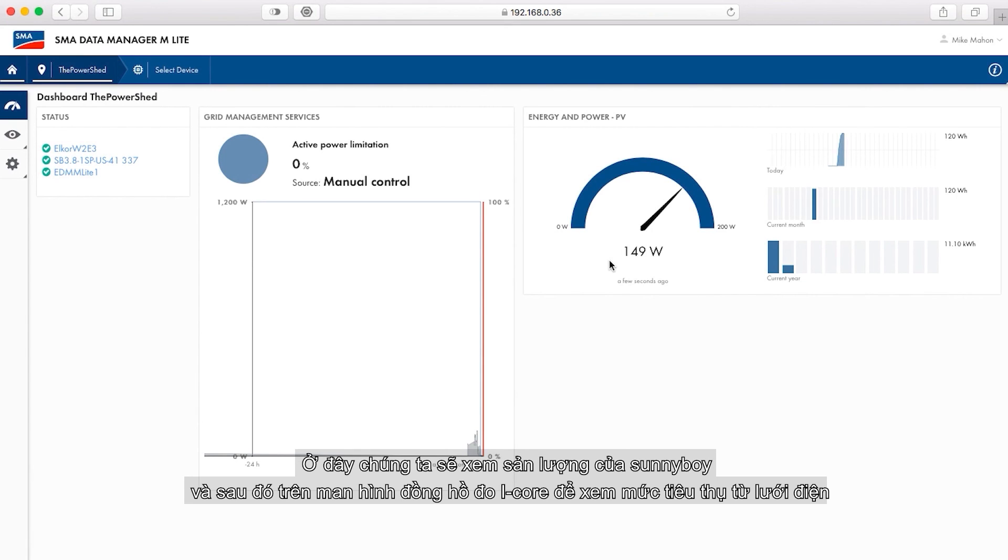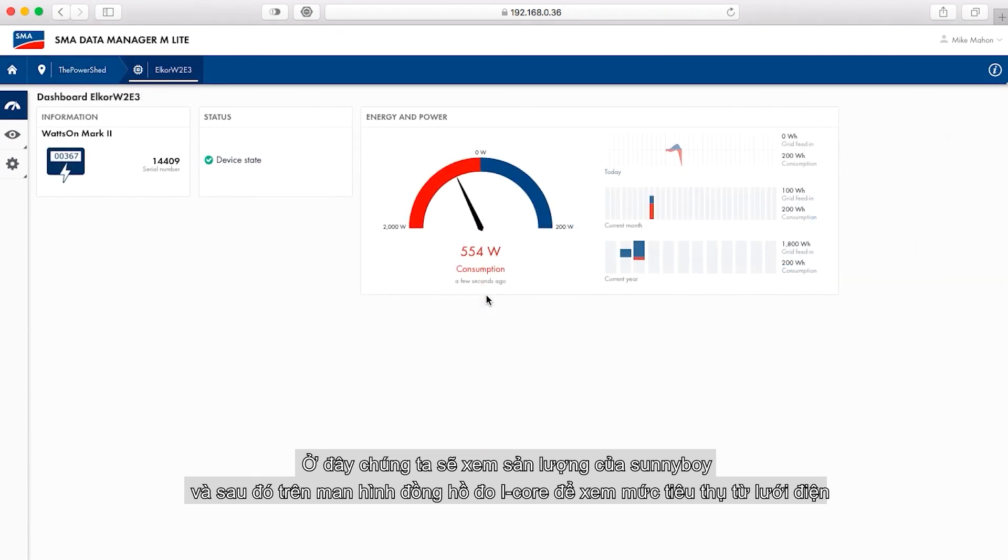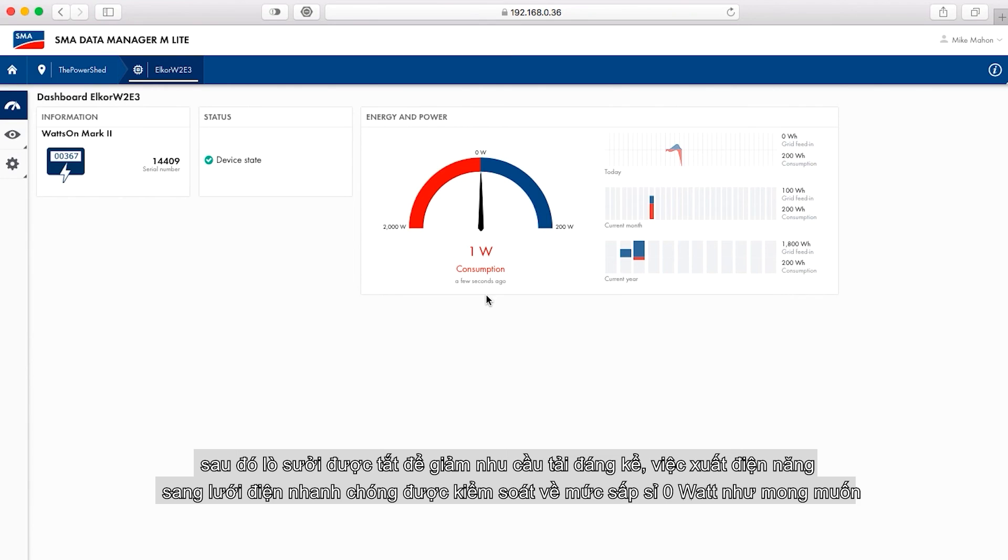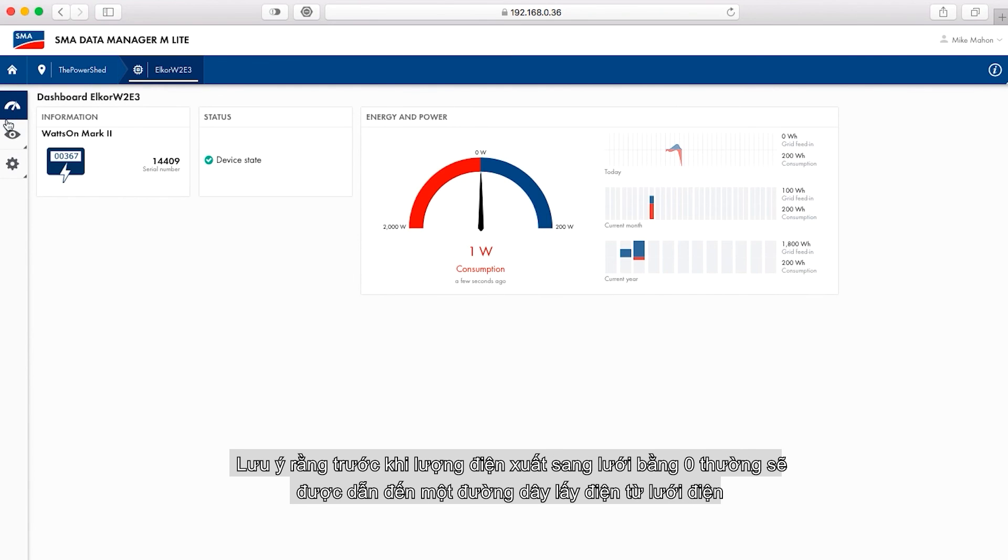Here we see the sunny boy production and then on the Elkor meter screen, the net consumption from the grid. Then a heater is turned off to drop the load demand significantly. The swing to grid export is quickly controlled to approximately zero watts as desired.